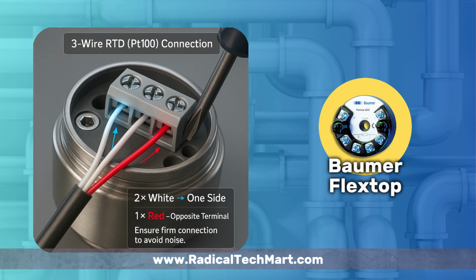Next, wire the RTD sensor. Connect the 3 leads of the PT100 sensor, 2 white and 1 red, to the input terminals as shown in the wiring diagram. 2 white wires go together on one side, and the single red wire goes to the other terminal. Tighten all screw terminals properly to avoid noise or loose contact.